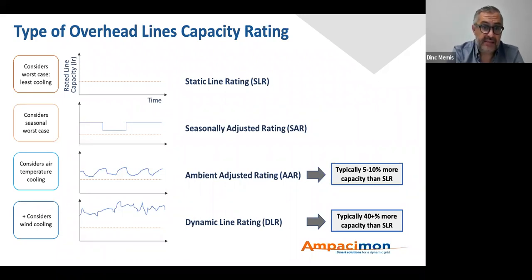The third one is the ambient adjusted rating, which is a rating computed with ambient temperature, simulated sun radiation and minimal wind speed defined by the utility. They are proven to provide 5 to 10% more capacity on top of the static line rating, but it is really very risk-free and it leaves some capacity gains on the table.